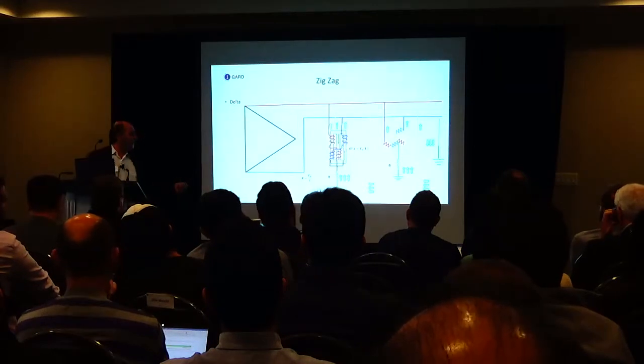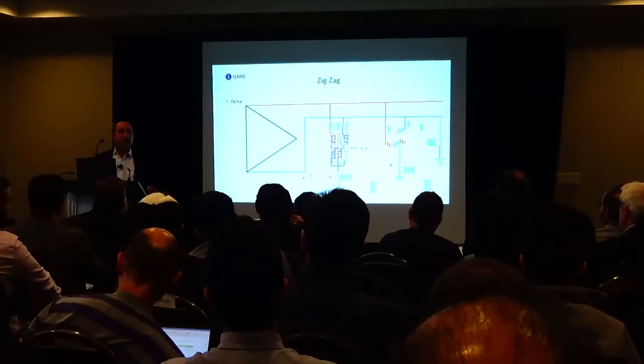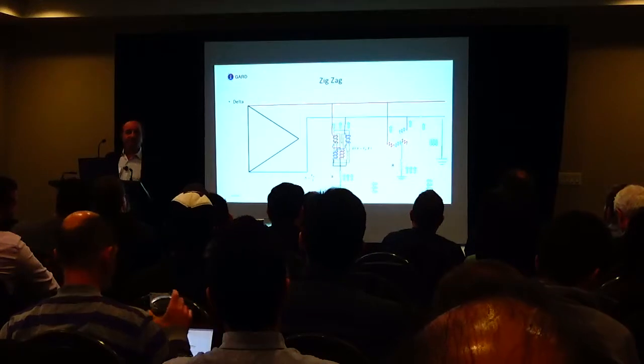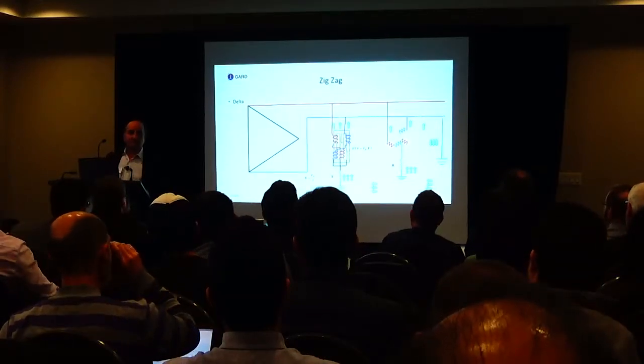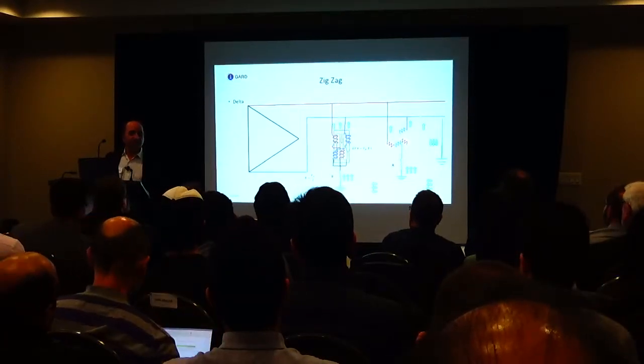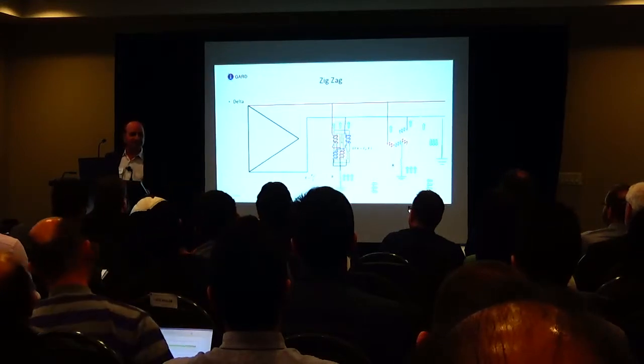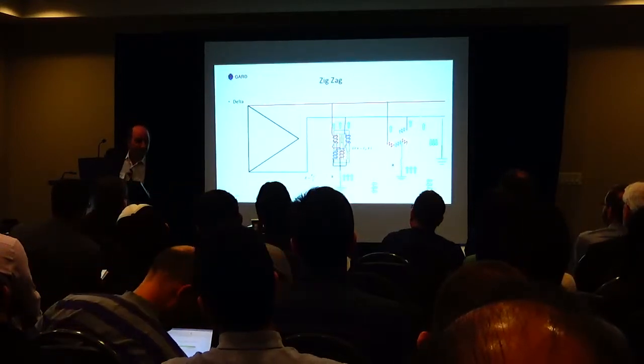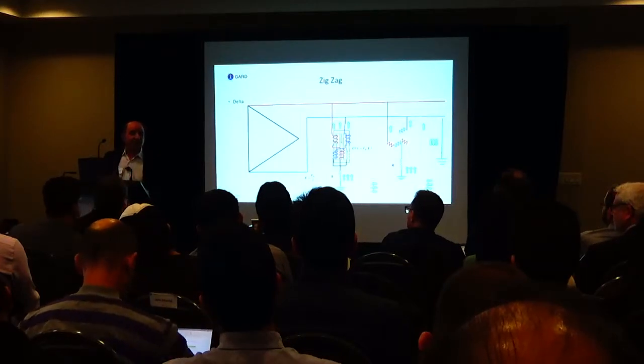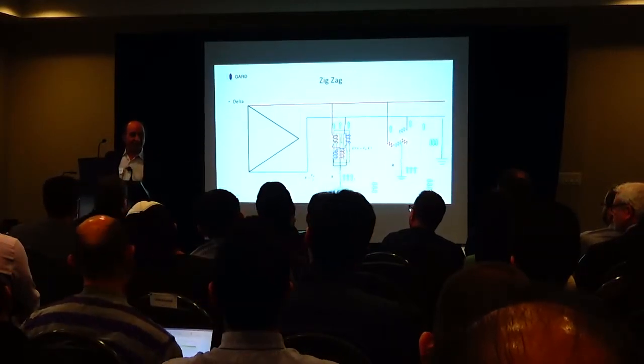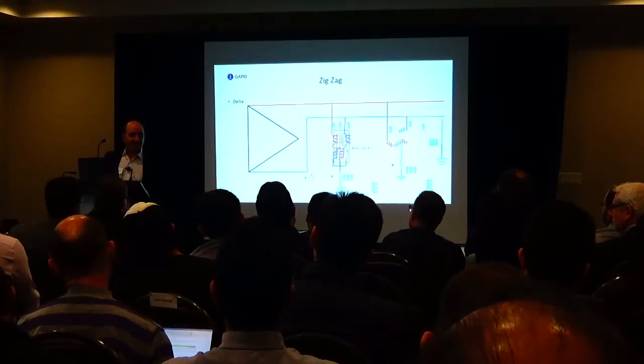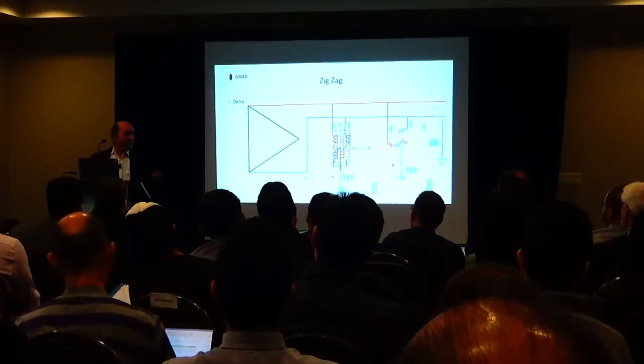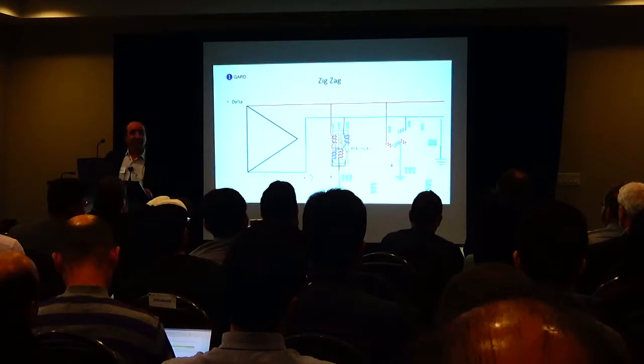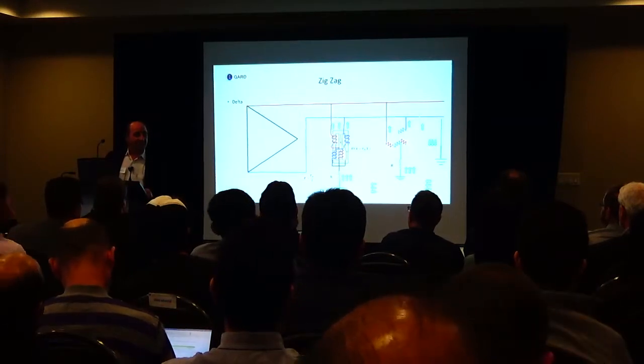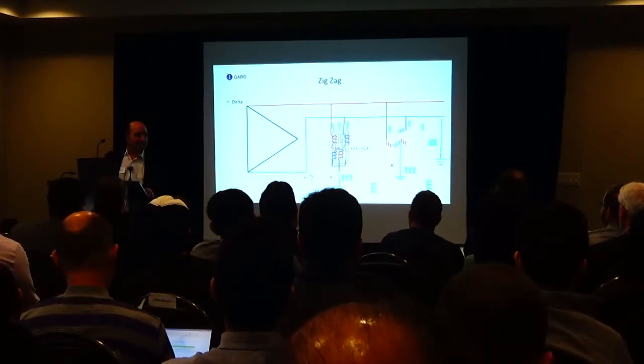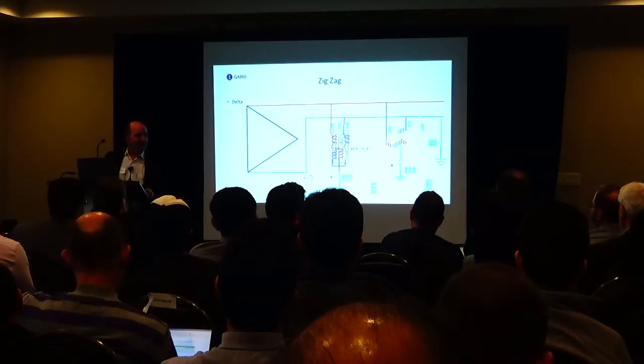If you have a delta system and you want to convert it to a resistance grounded system. Does anybody have delta systems? You have a delta system. Why do you have a delta system? It's just, when the generators are disconnected, that's when it's still not grounded. But otherwise, when the breakers are closed, it's all grounded. Okay. And you, why do you have a delta system? Same system? You inherited it. You inherited the delta system.